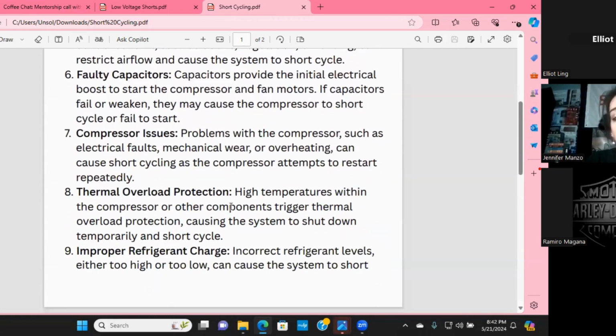And then compressor issues, obviously, this is really worst case scenario. So compressors can go weak before they go dead. More of what we see is that copper plating that causes acidity within the compressor, and that just stops it right in its tracks. But sometimes that doesn't happen. Sometimes it doesn't automatically short to ground when the windings are screwed. It just keeps running.